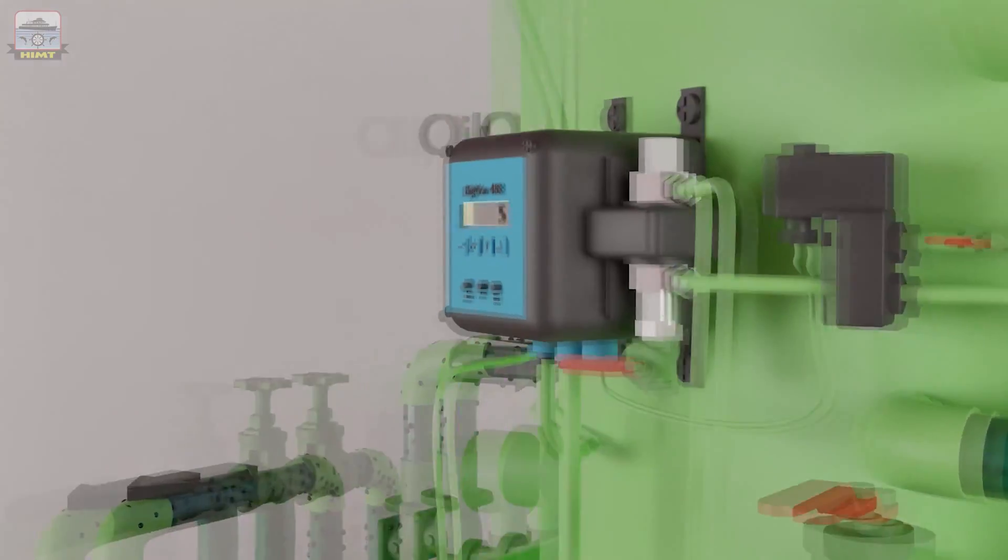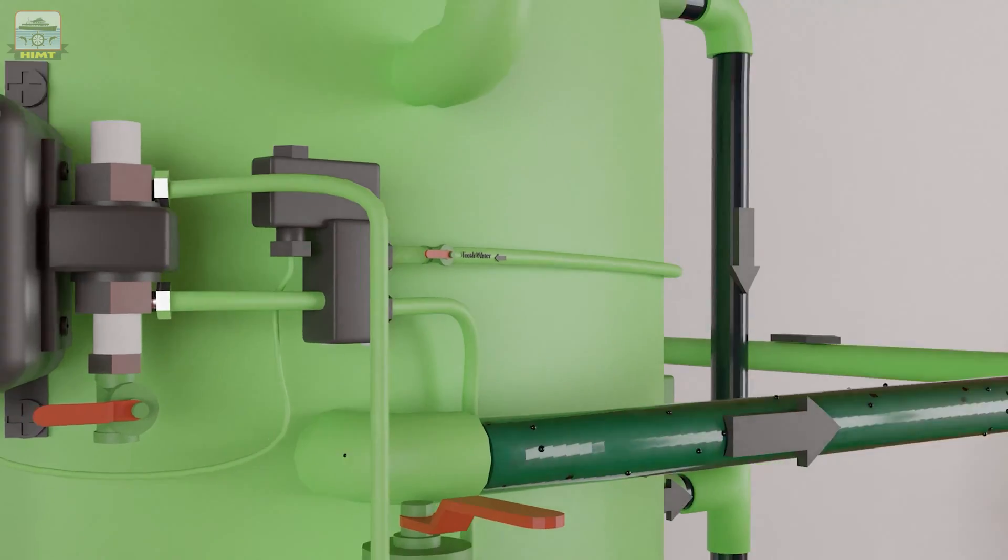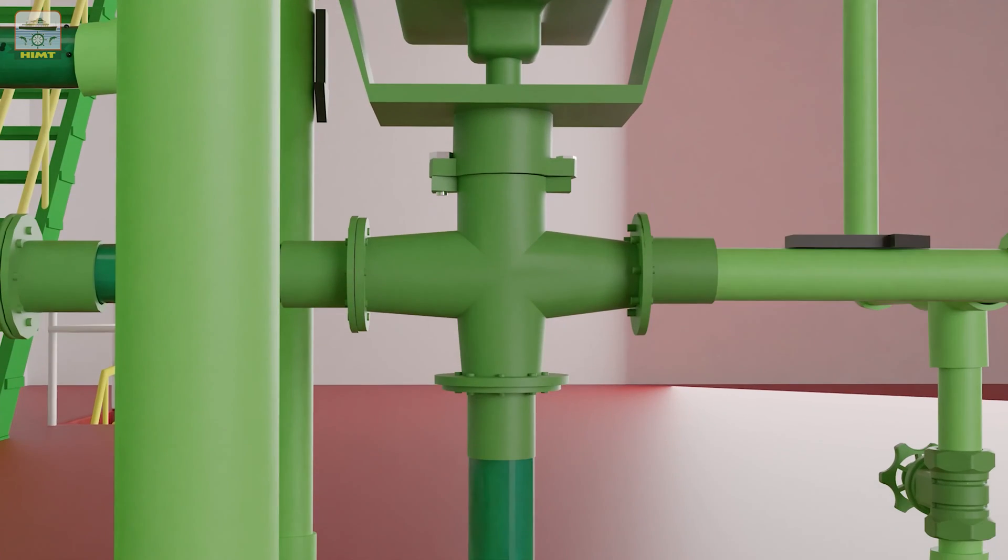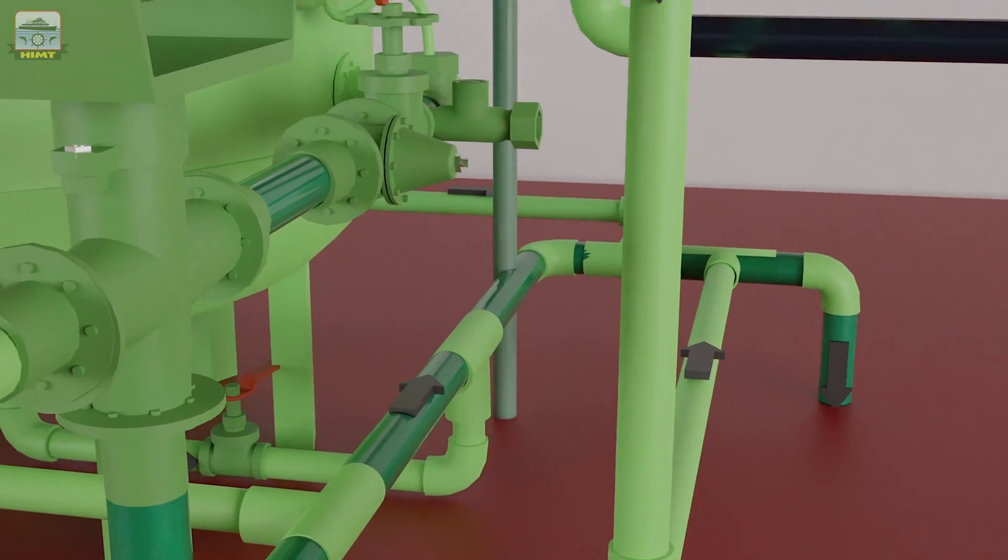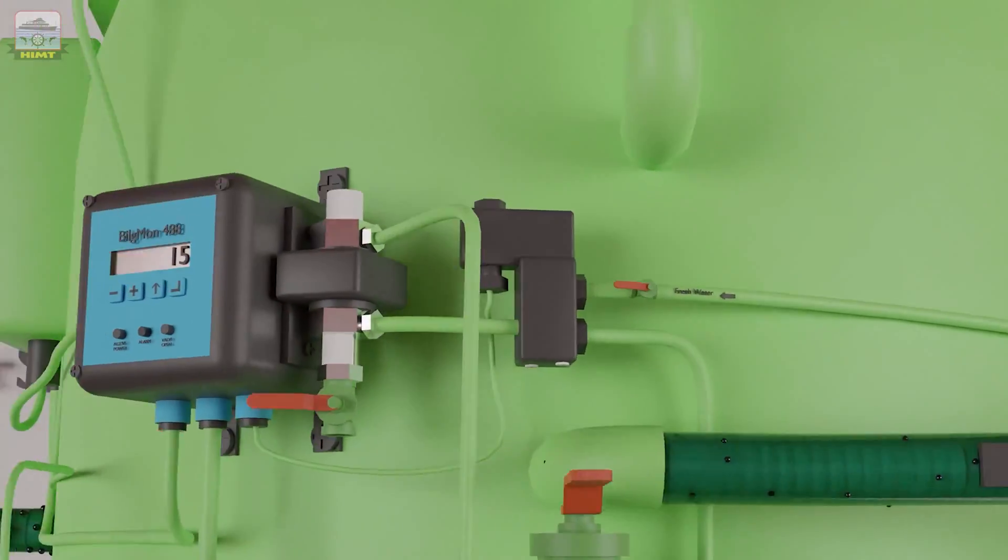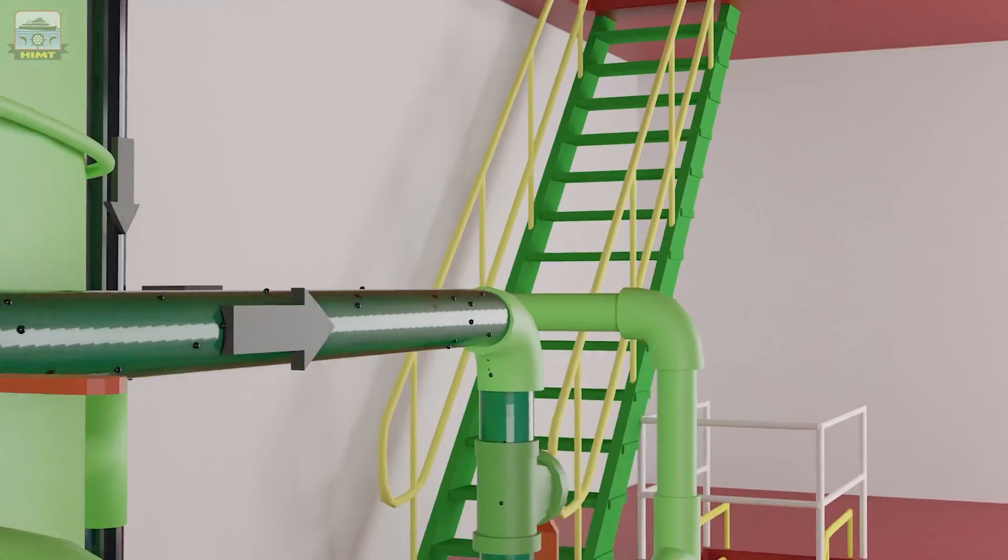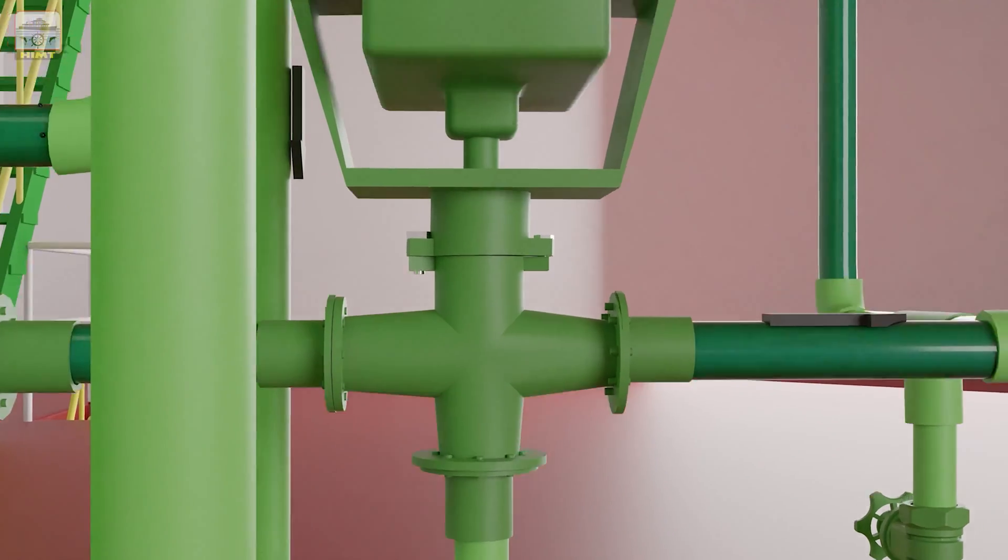If the oil content meter senses over 15 ppm of oil, it closes the discharge to the overboard. Once the oil content is below 15 ppm, the discharge reopens to the overboard line.